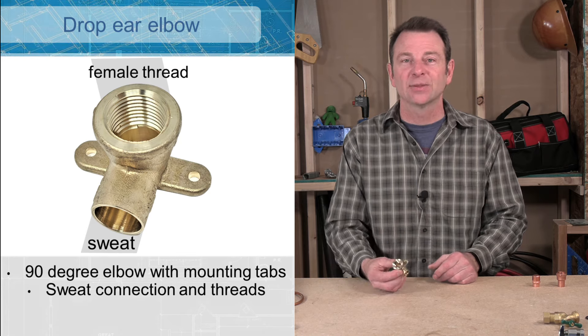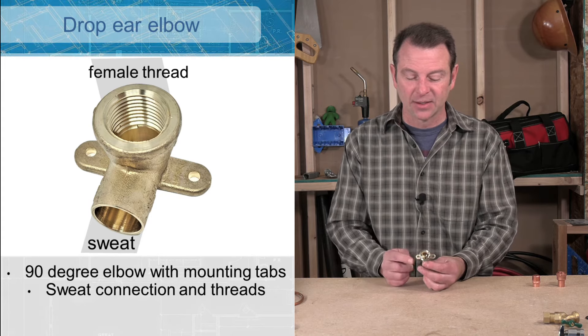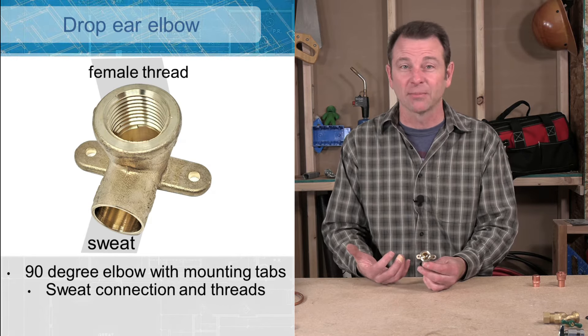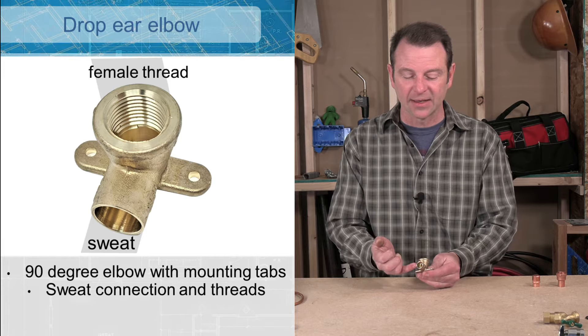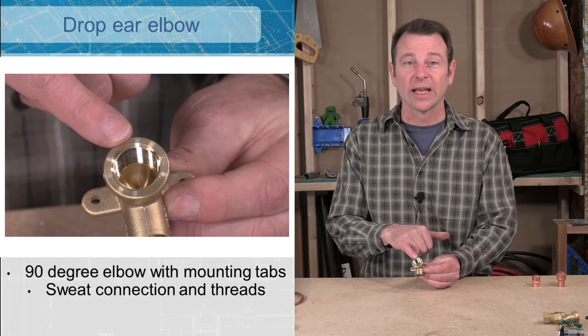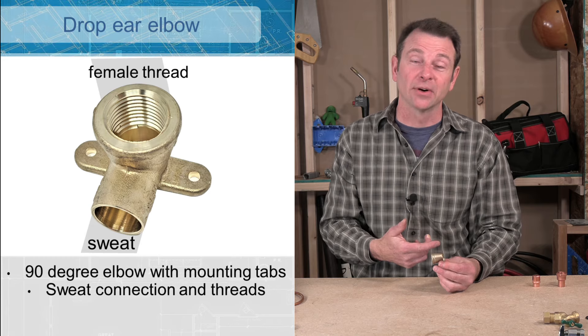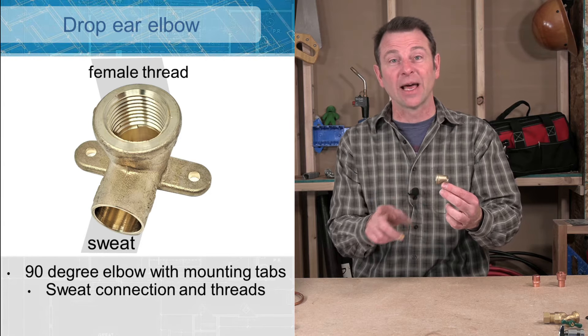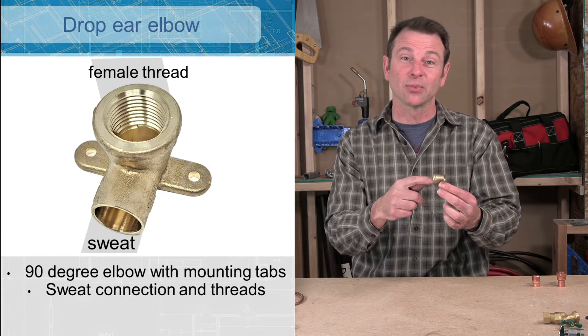I have another transition fitting here. This one has a funny name. You would call it a drop ear elbow. And it has a couple of tabs on it with holes that you would screw it to some framing. This would secure this pipe. We're always trying to secure our pipe to keep it in place and keep it from breaking loose and leaking. And it also has a sweat fitting on this side and a female thread NPT thread on this side. This is half inch NPT. A good example of when you would use a drop ear elbow would be in a shower. This is a common part. The pipe would come up from the valve and then your shower head would come out of this connection right here. A typical shower head would have a screw in or a male NPT thread connection that would go in here. That's a rundown of some basic fittings.